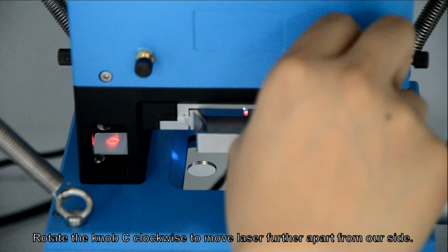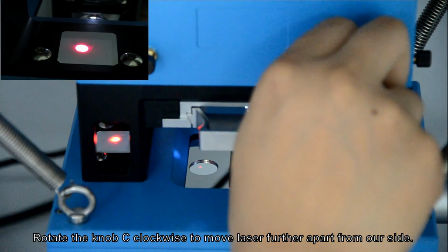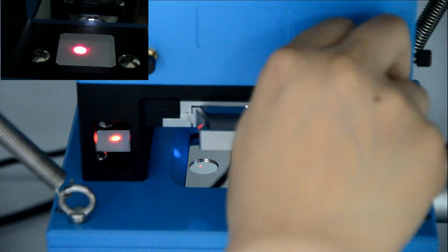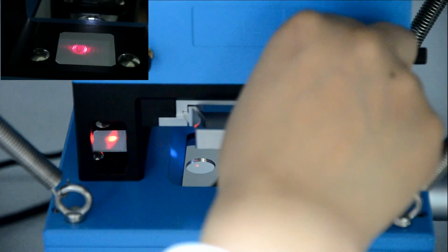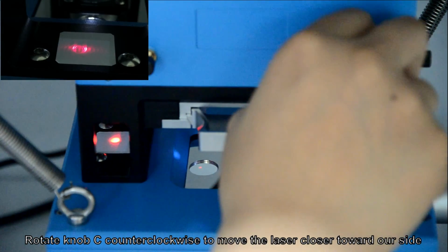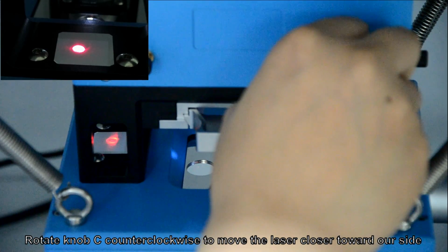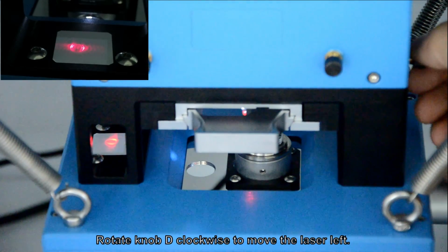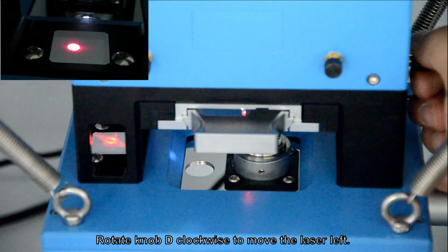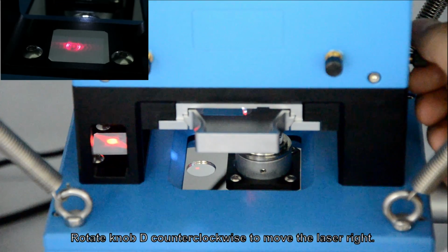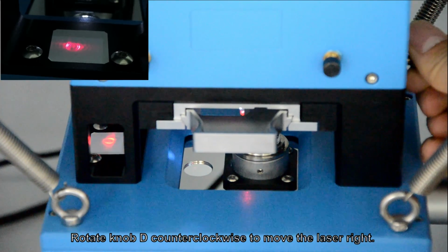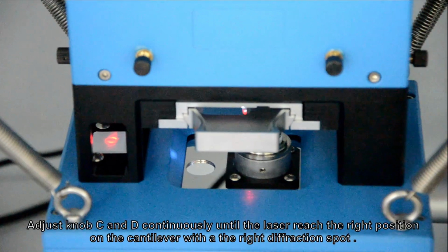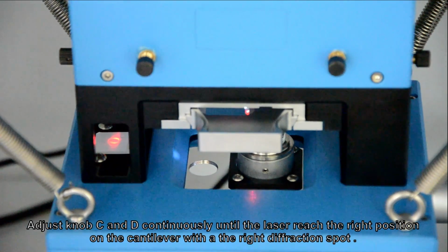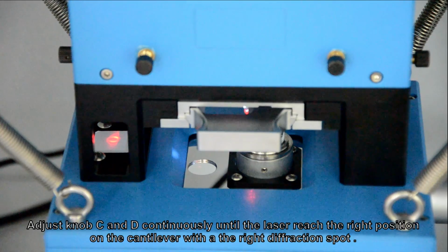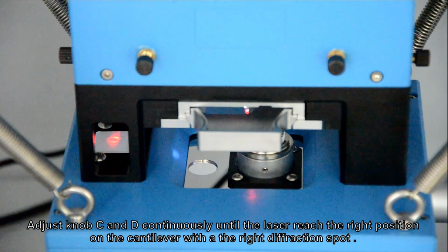Rotate knob C clockwise to move laser further apart from our side. Rotate knob C counterclockwise to move the laser closer toward our side. Rotate knob D clockwise to move the laser left. Rotate knob D counterclockwise to move the laser right. Adjust knob C and D continuously until the laser reaches the right position on the cantilever with the right diffraction spot.